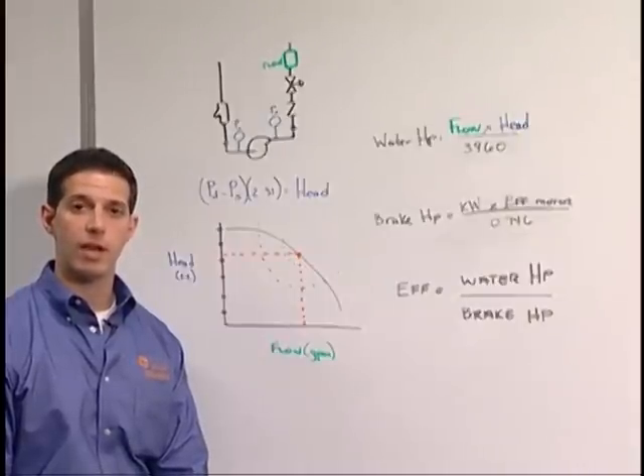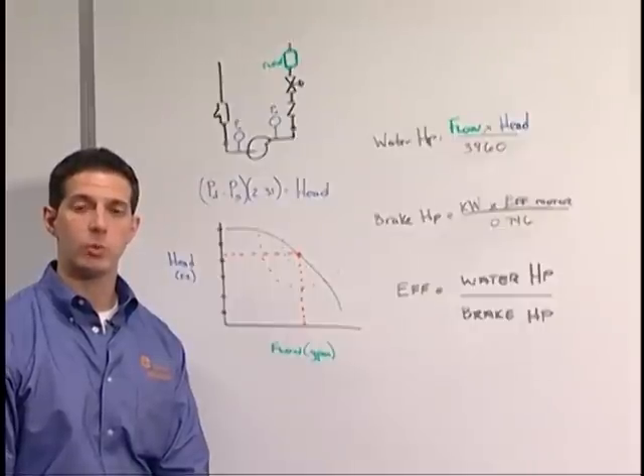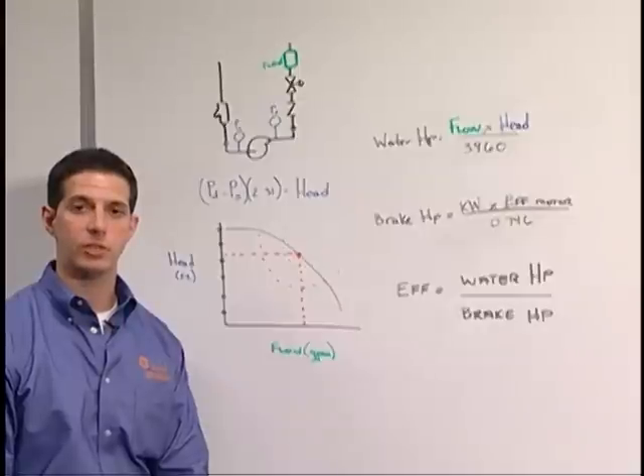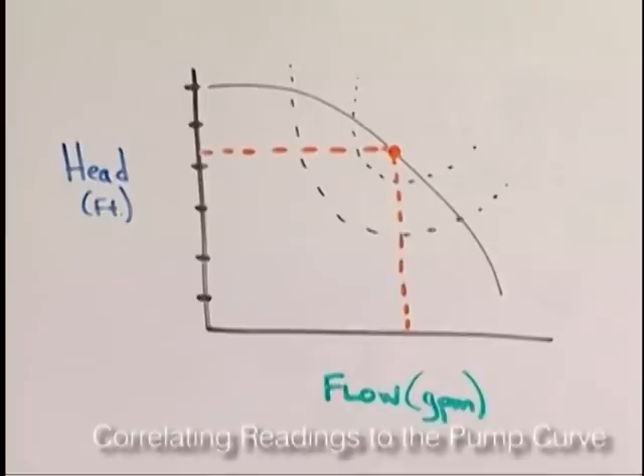Once data is collected there, slowly open the discharge to about 50% of the as-is condition. That data can then be correlated to the pump curve.